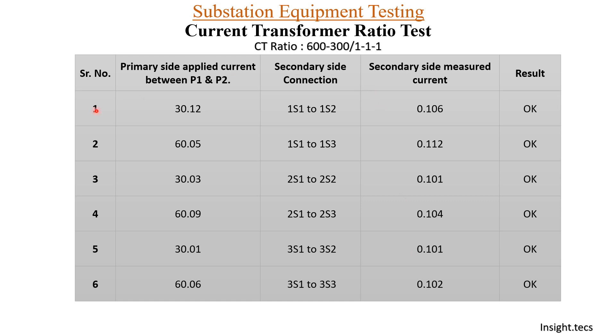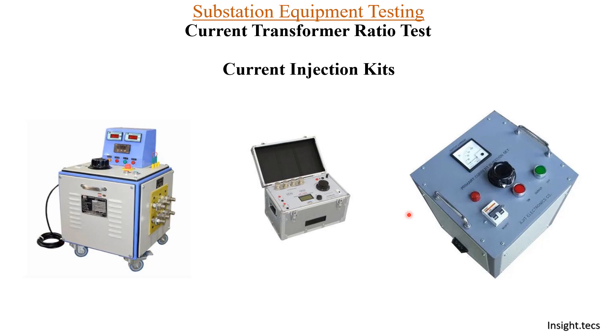You can see here a compiled table of the different readings we have measured — the primary amperes, the secondary connections, and the secondary current obtained. We have learned the basic concept of how the CT ratio test is performed. In present conditions, current injection kits are available in the market, and using those kits you can easily measure the ratio of the CT.